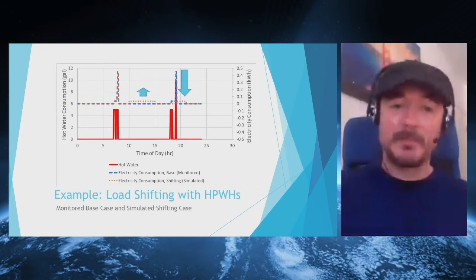So this is an example where load shifting didn't have as much impact as we wanted. We wanted no electricity consumption during the peak period. But since we didn't have to use the resistance elements, it had a big impact—not perfect, but big. This next slide just adds arrows showing the impact we're able to see on that particular day because of simulating the load shifting case using the monitoring data. We can really directly compare the base case, what happened on that day, to the load shifting case and what would have happened.